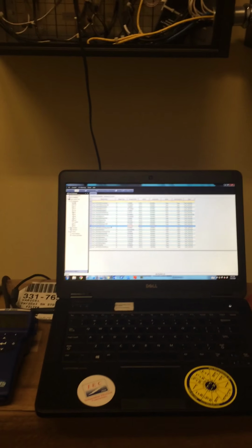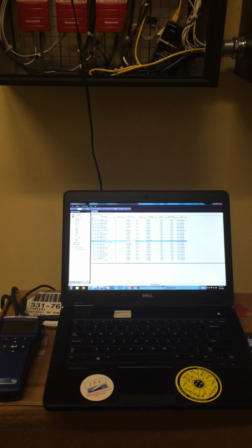Well, anyway, I got a call basically saying that the discharge air temp was kind of high, and that the cooling valve actuator for the chilled water coil was at 100%. And as you can see, my discharge air temp is at about 69 degrees.